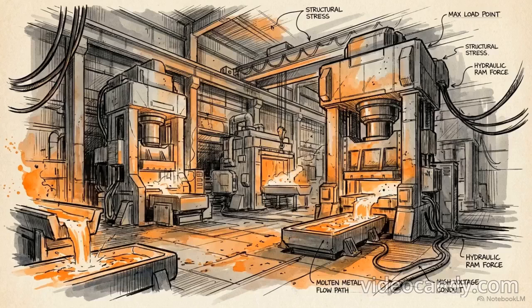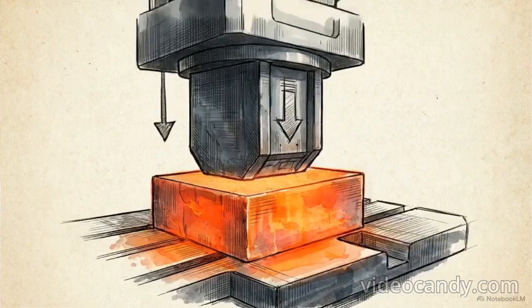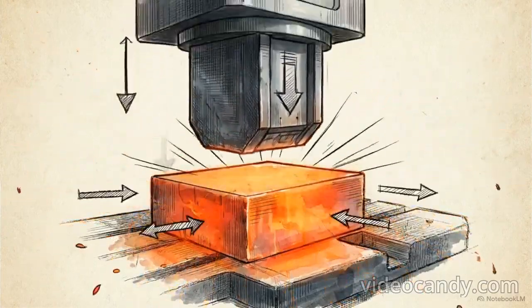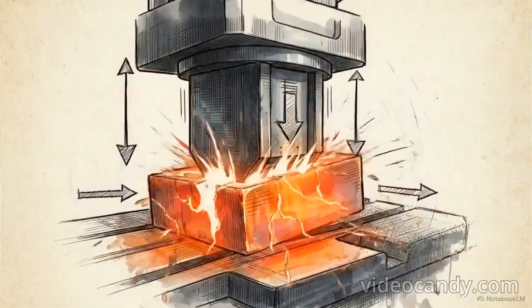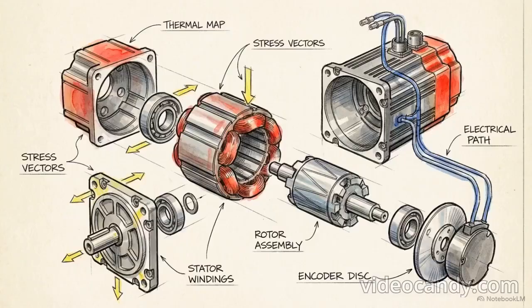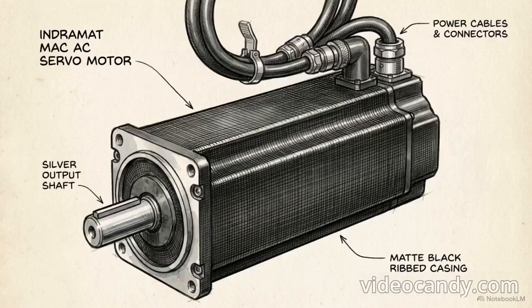Industrial environments subject these motors to extreme mechanical violence. A stamping press slamming down into solid metal generates repetitive, high-frequency shock waves that travel directly back into the motor's driveshaft. Specifying a servo for this environment involves reconciling a strict matrix of thermal limits, mechanical constraints, and electrical variables.